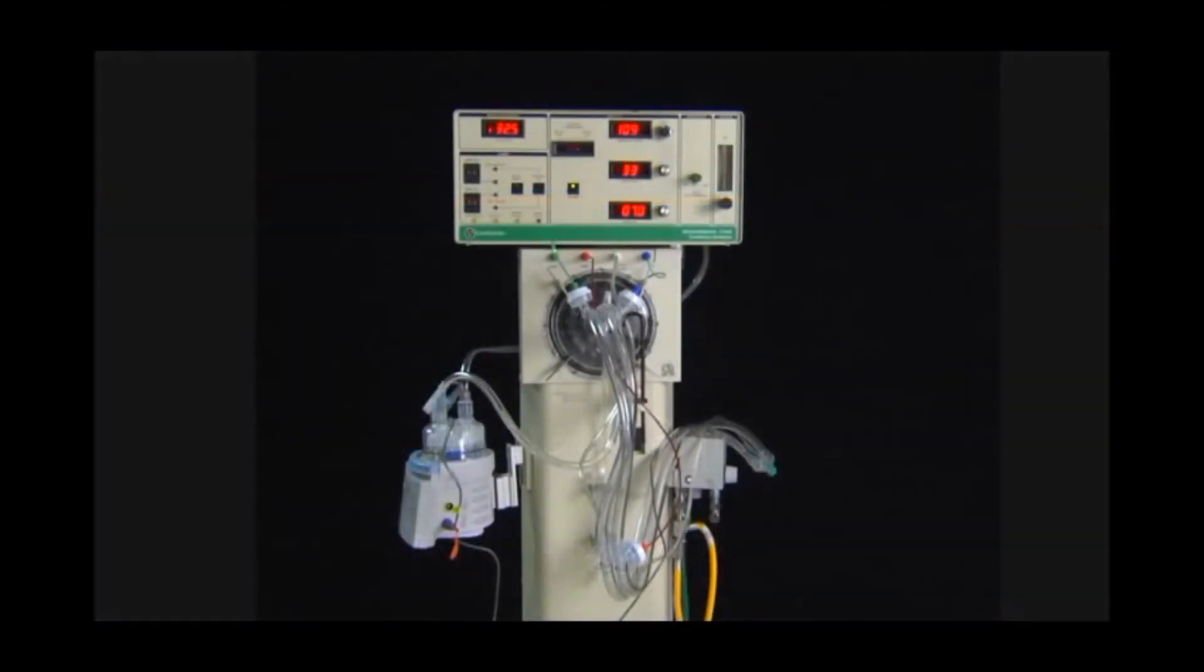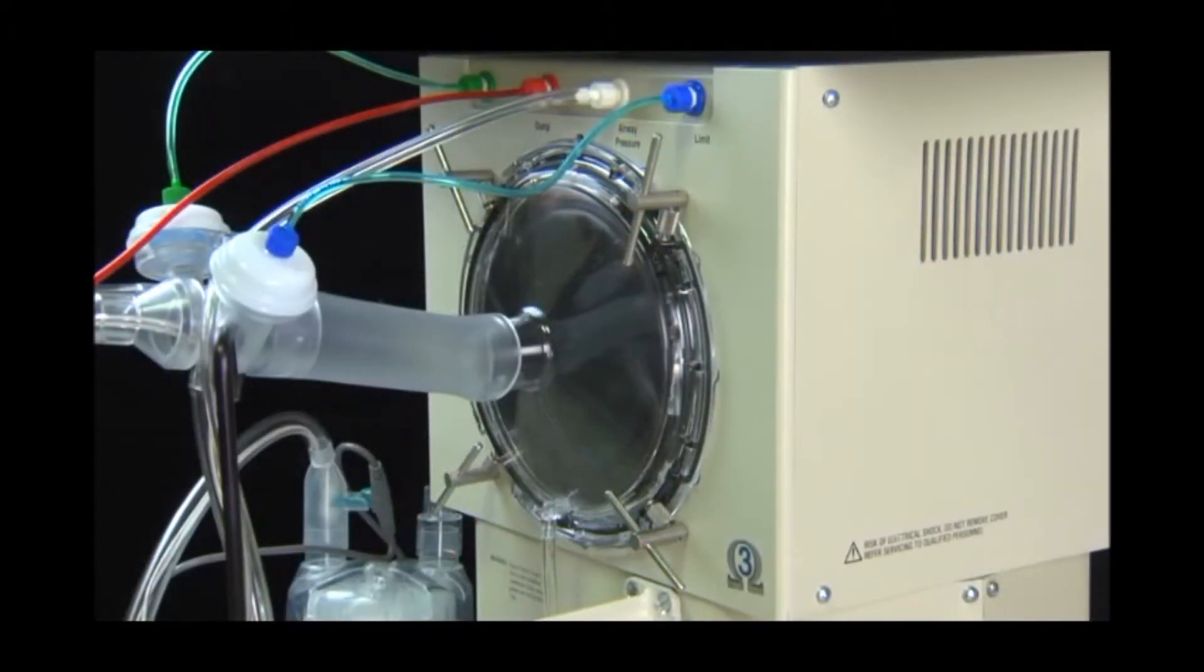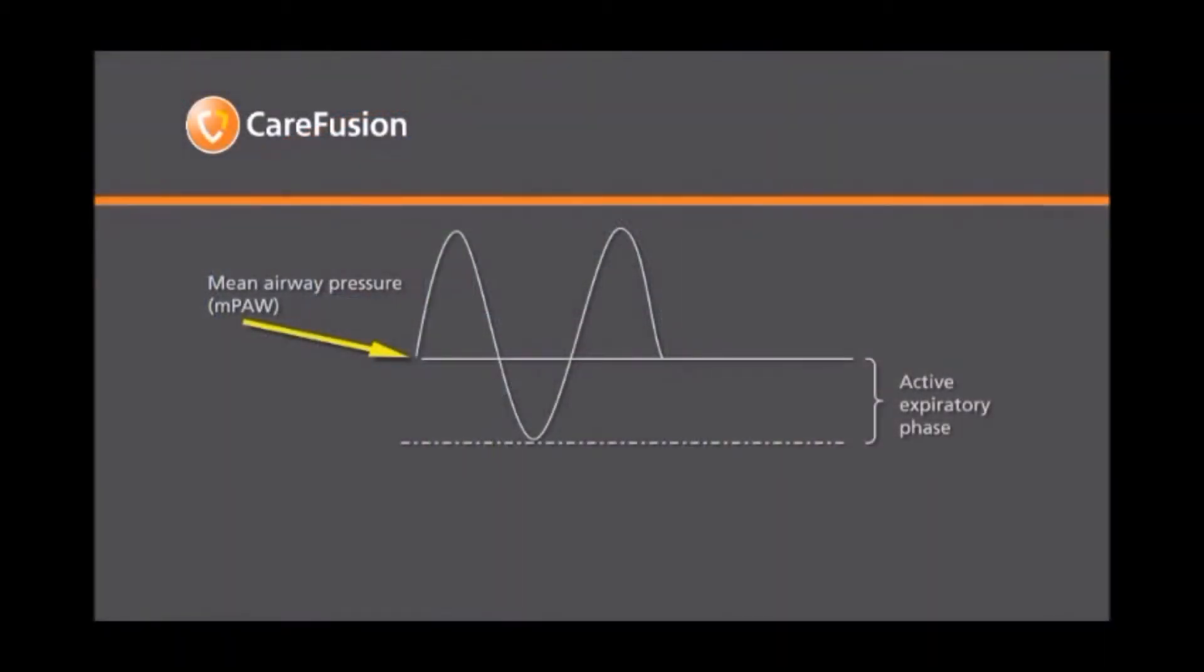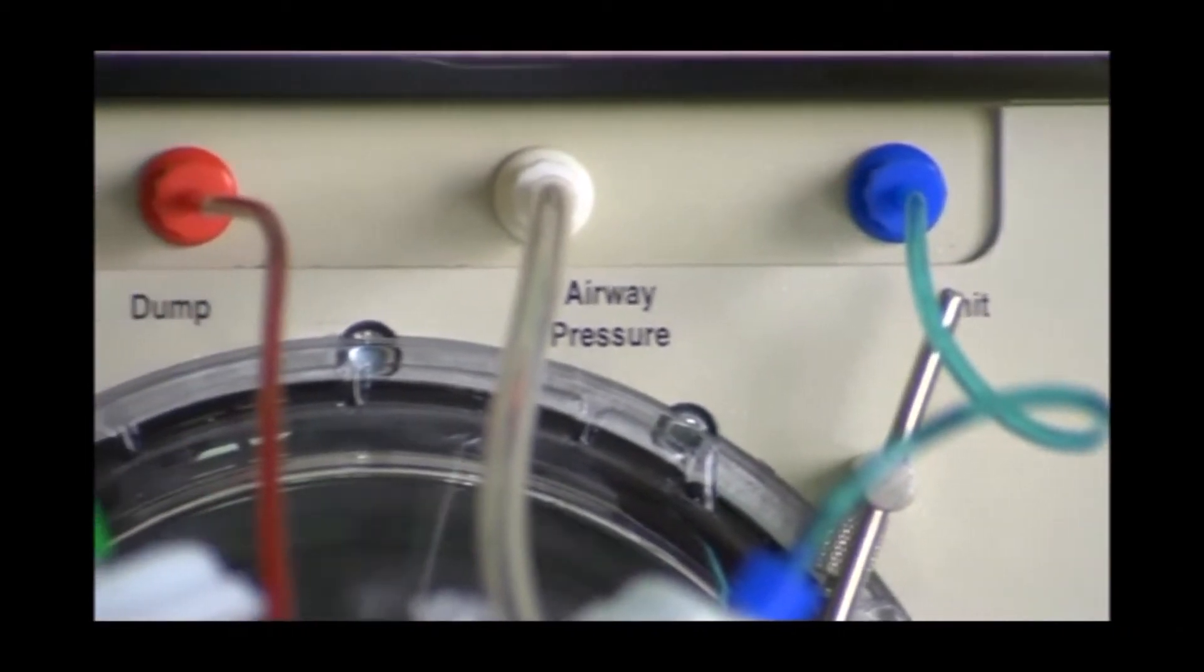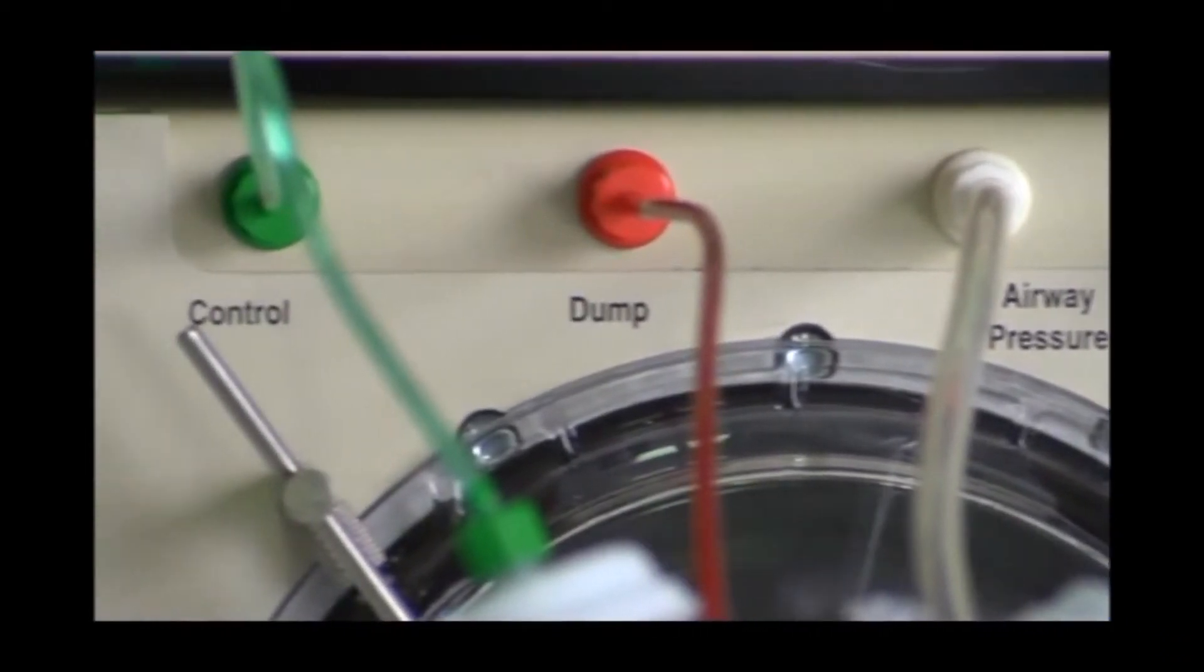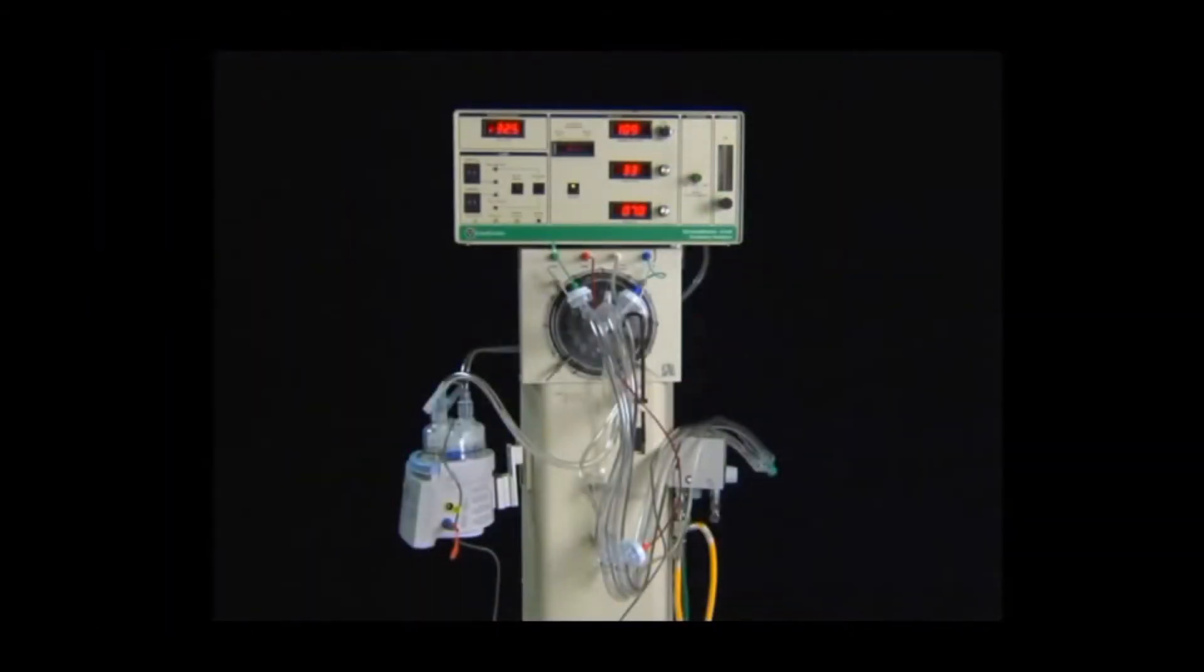While several techniques employ passive exhalation, similar to a conventional ventilator, high-frequency oscillatory ventilation, or HFOV, uses an active expiratory phase. This distinctive feature is what truly defines high-frequency oscillatory ventilation. The CareFusion 3100A and 3100B are very simple devices. These are essentially large CPAP generators with a piston diaphragm oscillator attached. This system allows the 3100 to gently inflate the lungs while superimposing oscillations to ventilate the patient.